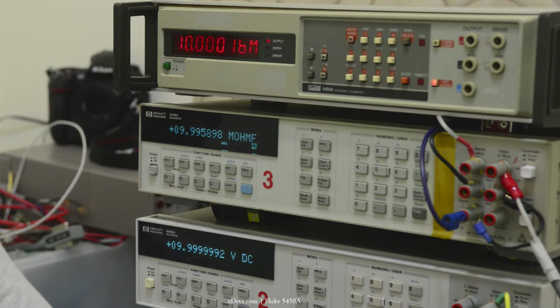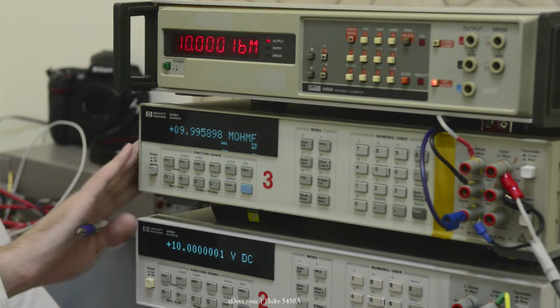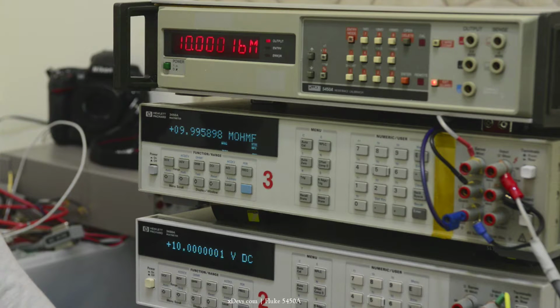10 megohm, let's wait for a second sample. In high megohm resistance values, the actual meter spec is worse than the resistance standard, because you have a lot of noise and the currents are very low, so there are a lot of different effects in play.